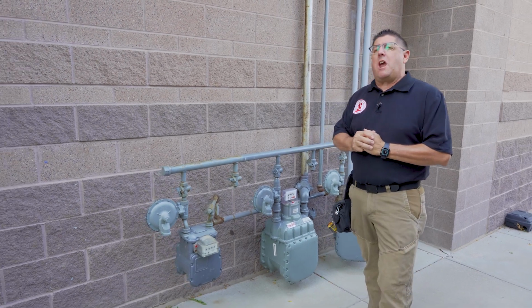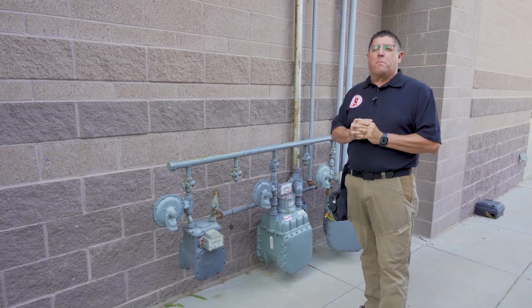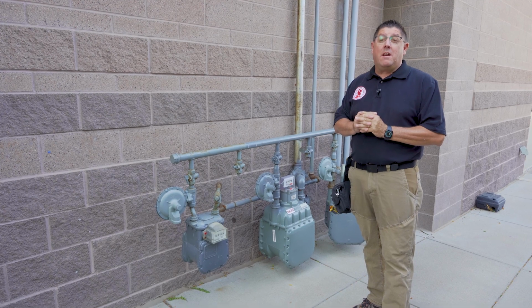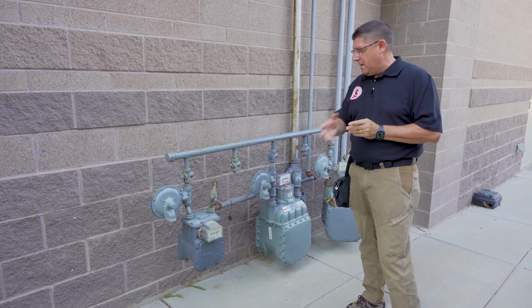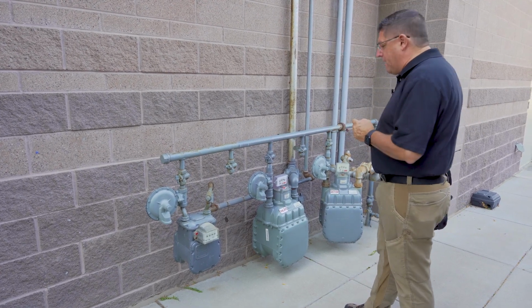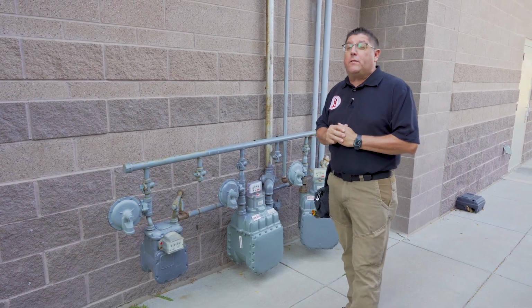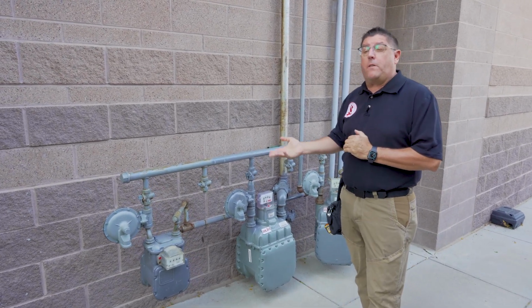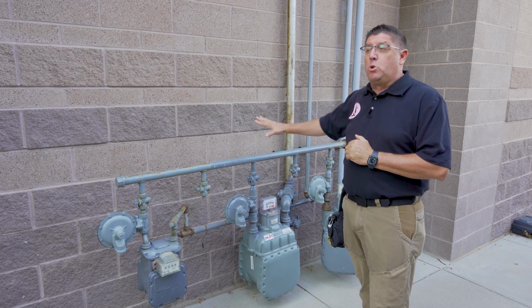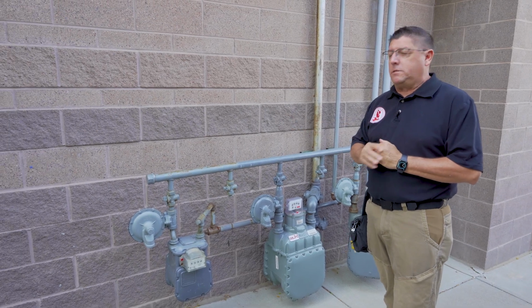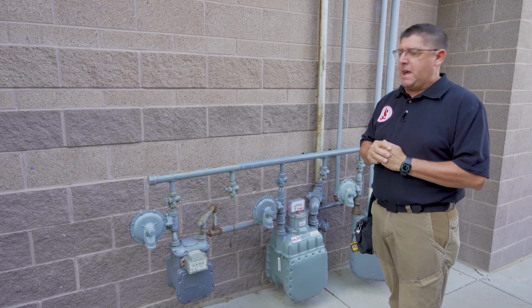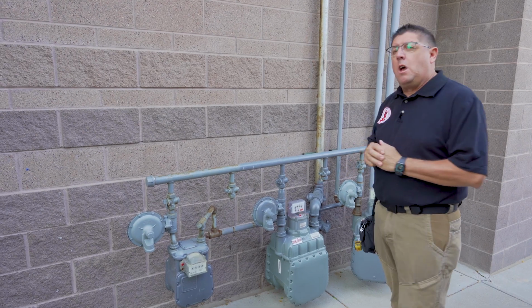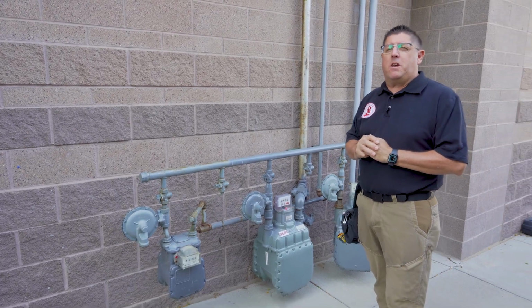When looking at the standard, the gas meters, when multiple are present, should be identified with some form of labeling. In this particular case, I don't have any labeling. We do have two different sizes here because two of the spots in this building are restaurants and one of them is a standard office space, and so they have larger meters for the amount of gas being used.